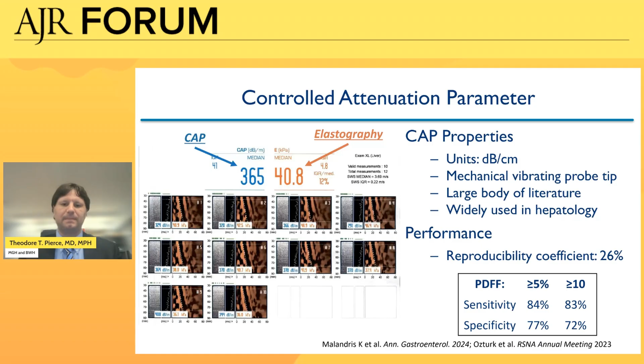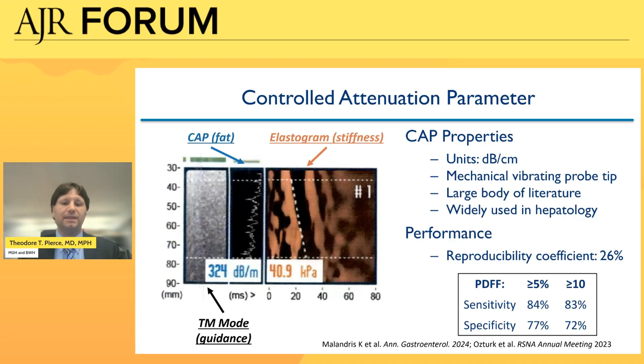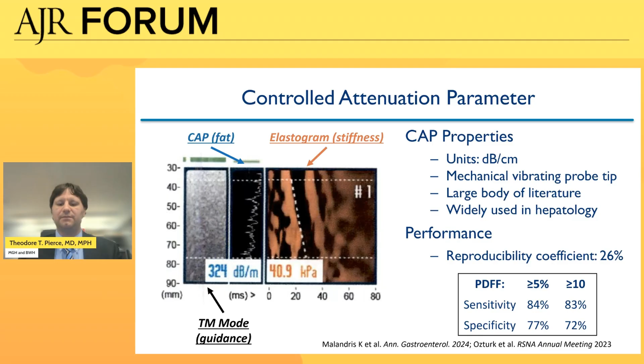Looking a little deeper into the measurement, this three-part panel reflects one individual measurement. On the left here is what's called the TM mode, and this is what's used for guiding the operator to correctly place the transducer. It's essentially an M mode image that we're familiar with. As you can imagine, this may be a little bit challenging to optimize the measurement region placement given the somewhat limited view. And can contribute to misplacement of the device and generating inaccurate values. In the middle panel is a plot of signal intensity versus depth, which is used to calculate the attenuation parameter. And on the right, this is the elastogram, the slope of that dark black band corresponding to the shear wave speed.